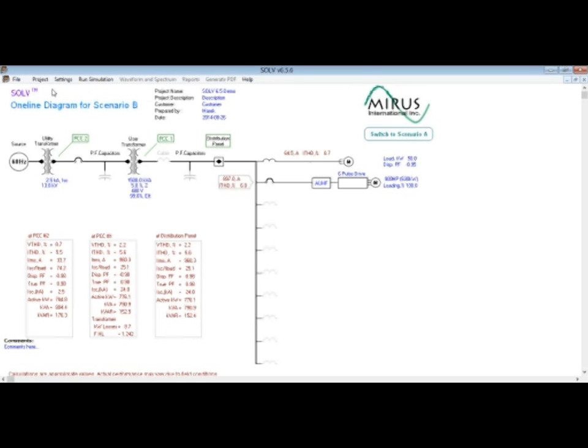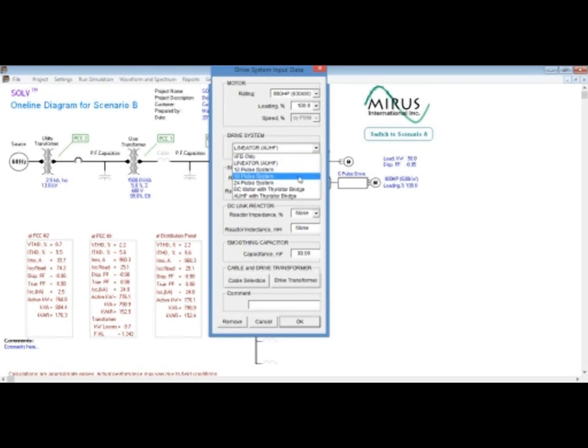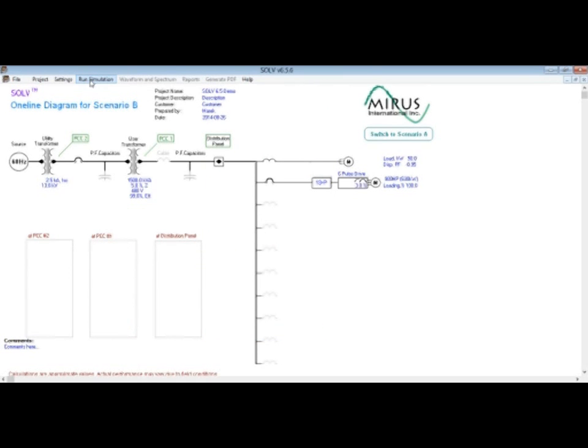And on the one-line diagram for scenario B appears, the single line appears active, and all data have been copied from the previous simulation. So to demonstrate multiple drive system performance, let's change the drive input data and choose the 24-pulse system for this VFD. So I click OK and run the simulation.